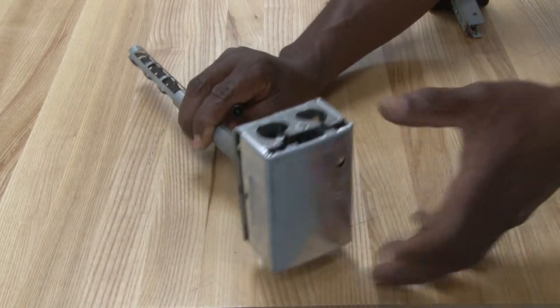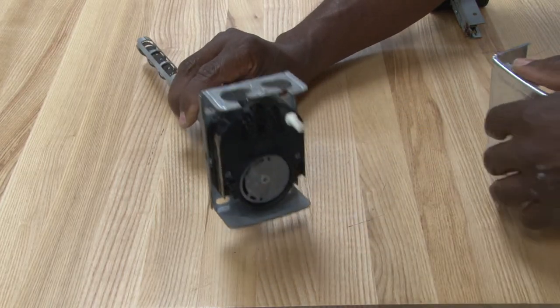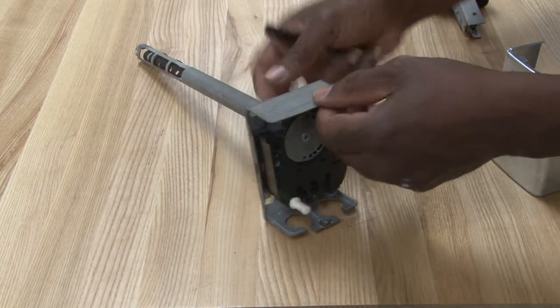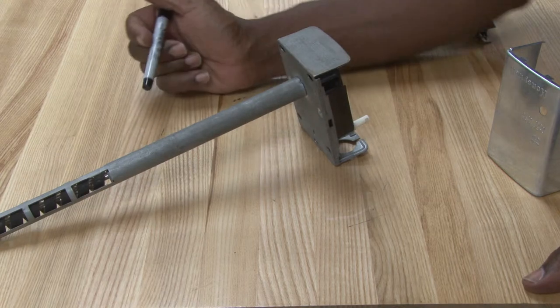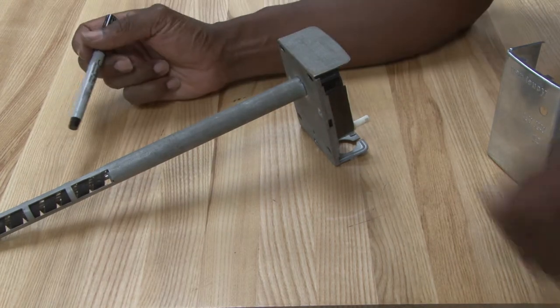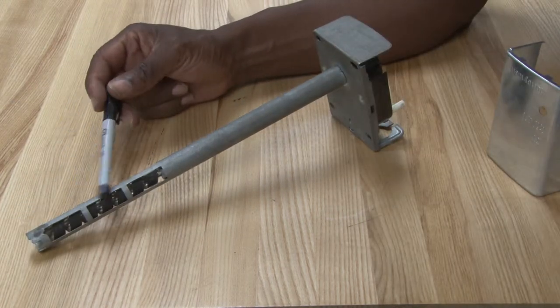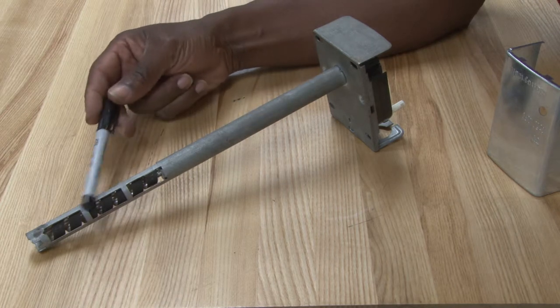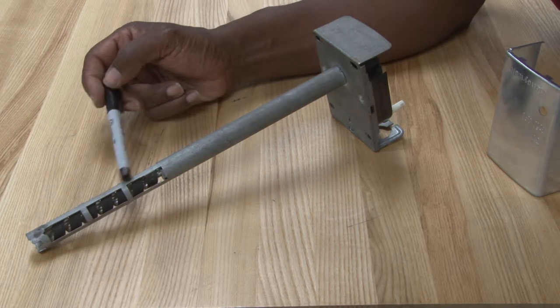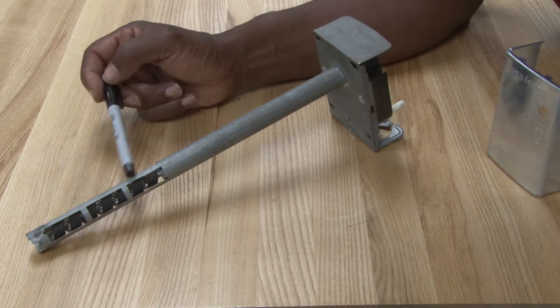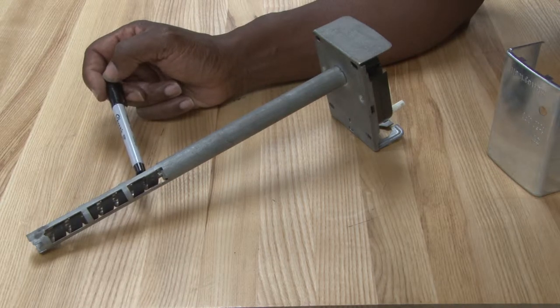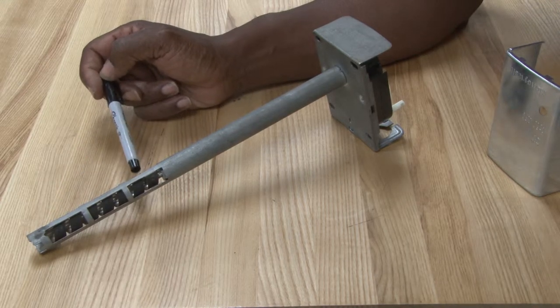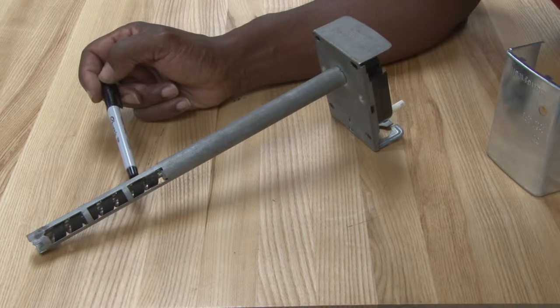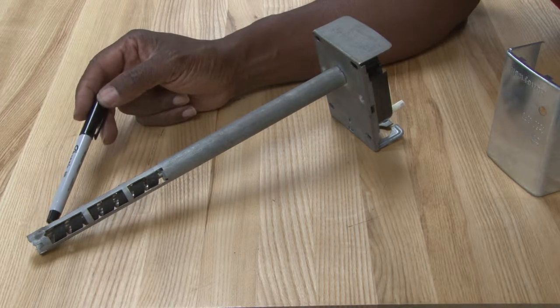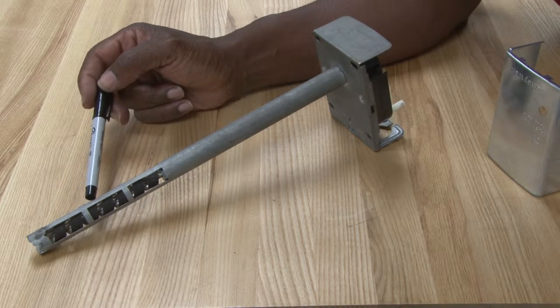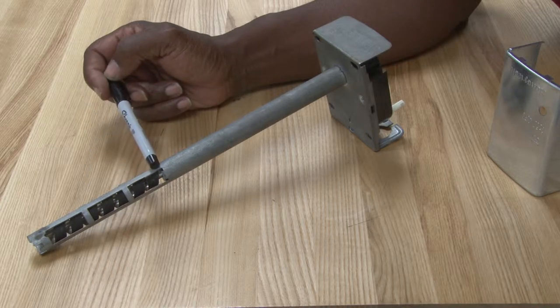This control is designed to maintain a high limit safety control. This is the shaft that actually inserts inside of your furnace. This is another bimetal coil that will expand or contract based on temperature. It's to protect the furnace from high temperatures, from getting too hot. It will open up a switch to de-energize your heating system.